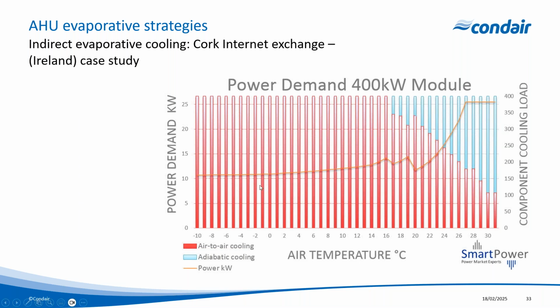What I want to point out here is if you look at the actual power demand, we max out at about 25 kilowatts to operate the system, but we are delivering 400 kilowatts of cooling. So a huge amount of cooling for a significantly low amount of energy input to the system.